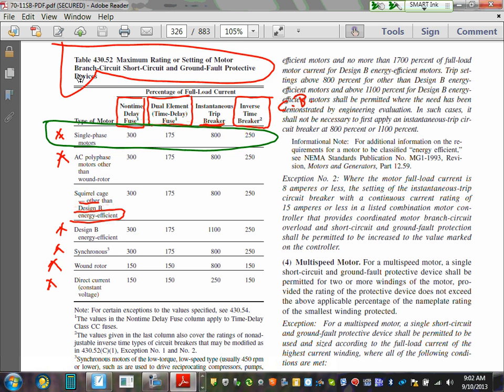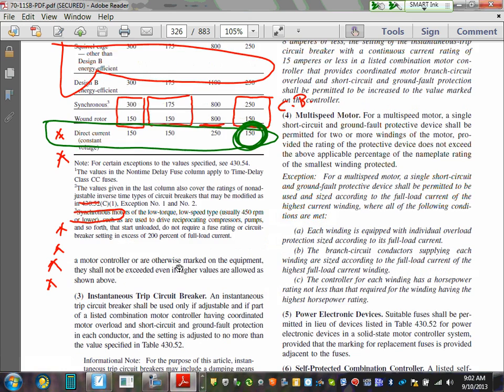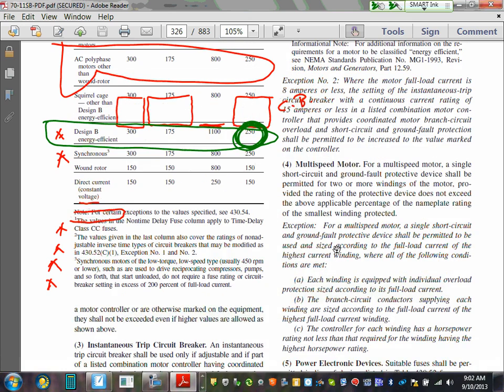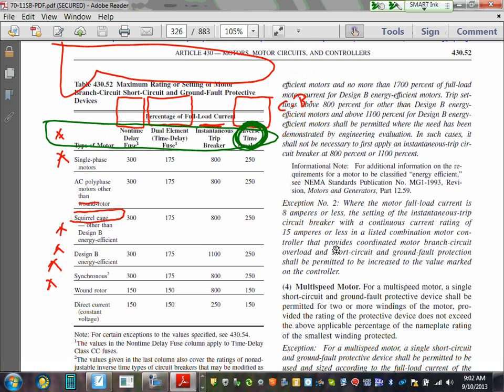All right, now, which one of these four types of overcurrent protection device would you like to use, Chad? I told you, I want a circuit breaker, the most common for single phase. Okay, for a circuit breaker, what's my multiplier? What's my multiplier for inverse time circuit breakers? Inverse time circuit breaker, 250. And if you read through all this stuff right here, guys, if you read underneath it, it tells you that if it's not a standard circuit breaker rating, you are allowed to go up.